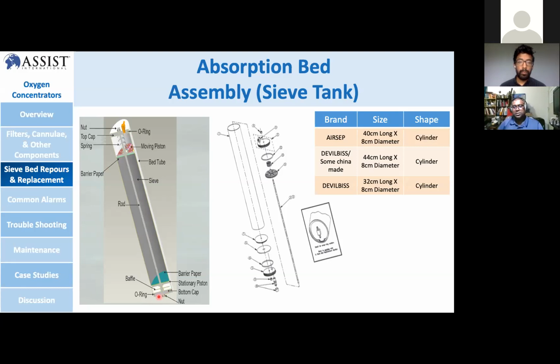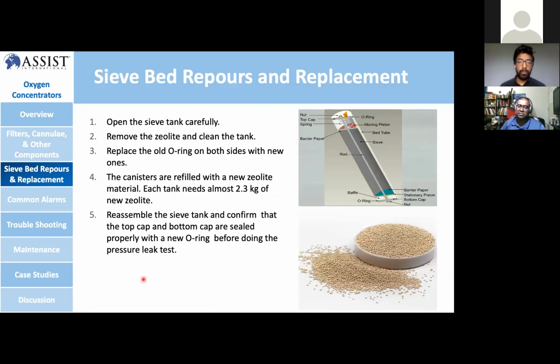So when you open the sieve tank, you have to be careful, because there's a spring that, if you don't press it properly, can pop off, and maybe someone is going to get injured, maybe yourself. So whenever you open this particular part, always use personal protective equipment. Then you remove the zeolite and clean the tank, and replace the old O-ring on both sides. Always remember to replace the O-ring, because the old O-ring may be damaged during the opening process, so you need to replace it with a new one. And the canister is refilled with new zeolite material; each tank needs almost 2.3 kilograms of new zeolite.